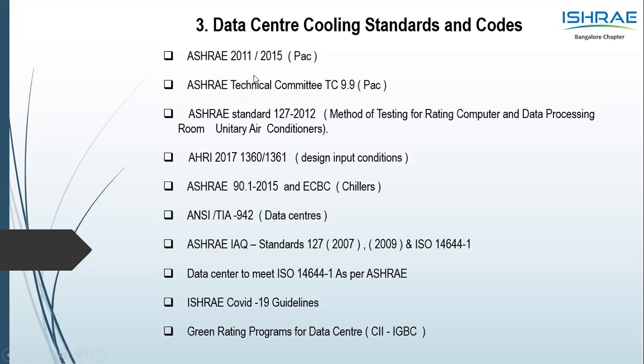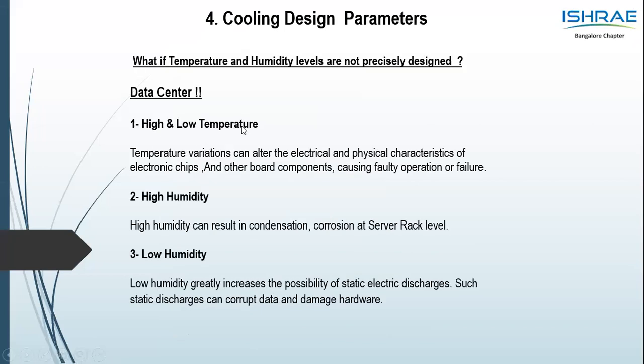First one, ASHRAE 2011, 2015, the technical committee, we will talk about that in the coming slide. Then the design input of AHRI and the ECBC norms on the chiller and the PAC, and the tier design and the R1, R2, R3, R4 as per ANSI TIA 942, indoor air quality as per ASHRAE norms, and the ISO standards of the air requirement within the data center, and the ISHRAE guidelines as well, which you will have to keep a check on because of the current pandemic issue. And we have a couple of green rating programs from IGBC, which talks about going green within the data center. So these are the cooling standards from the ASHRAE norms and other various societies' articles, which I have compiled for the benefit of all of us. So let's get into the next slide.